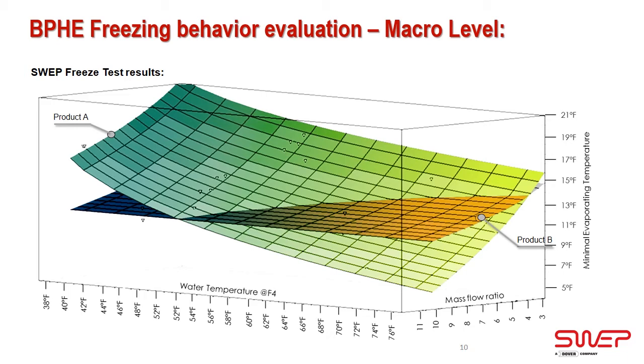It's maybe still tricky for you to say, but what we can see on this graph is design A has a lower minimal evaporating temperature for application with high water temperature and high mass flow ratio, which are operating conditions where it's almost no risk of freezing. For design B, we can see a more stable minimal evaporating temperature, and we can also see a lower minimal evaporating temperature for application with low water temperature and low mass flow ratio. As we will see later on, application with low mass flow ratio and low water temperature is what we can consider as the worst case for a heat pump application. So, based on this graph, we can conclude on design B as being the most suitable option for heat pump application.